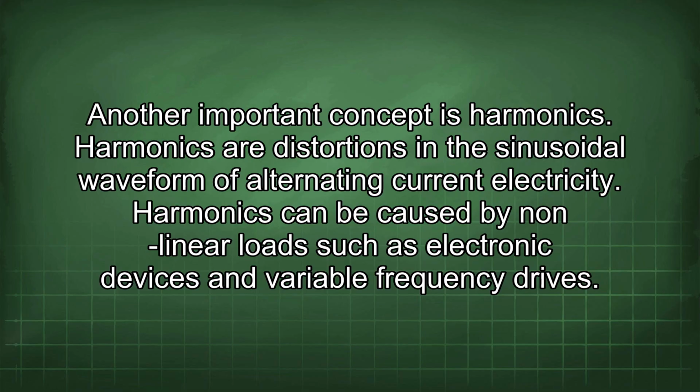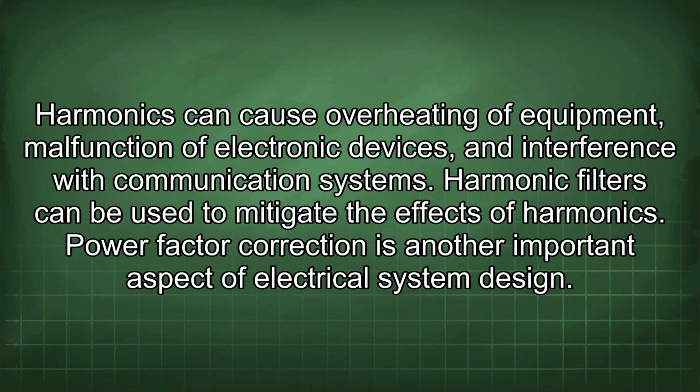Another important concept is harmonics. Harmonics are distortions in the sinusoidal waveform of alternating current electricity. Harmonics can be caused by nonlinear loads such as electronic devices and variable frequency drives. Harmonics can cause overheating of equipment, malfunction of electronic devices, and interference with communication systems. Harmonic filters can be used to mitigate the effects of harmonics.